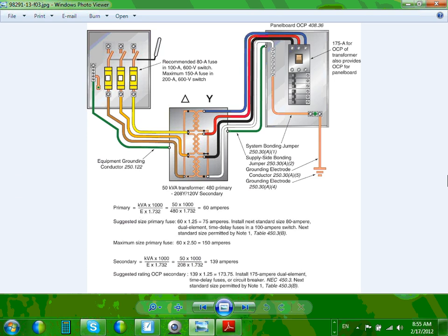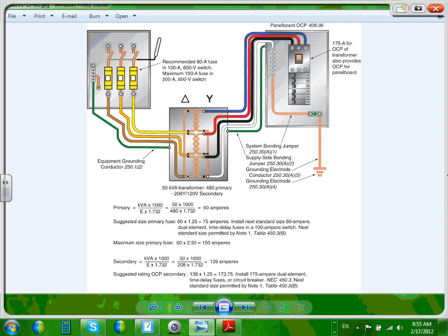This is if you have a system, you have a system 480. Your system is 480/277 volt, and you need to convert it into 208/120 volt. And everybody knows why would we do something like this? Because you need receptacles. How would you get receptacles if your system primary is 480/277?